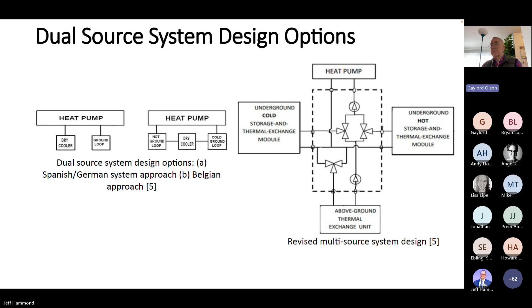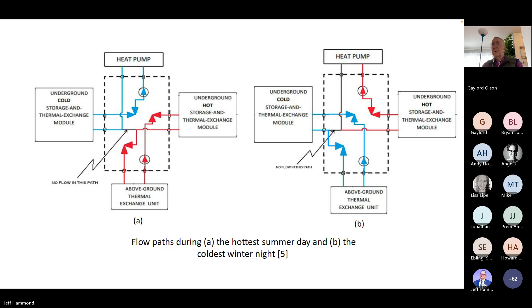Okay, so I think these are kind of repeats anyway, so I'm just going to zoom through these and you can look at them and think about them, but these are the 2 opposite seasons, hottest summer day and the coldest winter night. So you're getting warm water for the heat pump from the hot loop when you need it, and you're getting cold water from the colder ground loop when you need that. Hopefully you can have the water cold enough to have a very long duration of free cooling, so-called, or bypassing the compressor in the heat pump. So moving along to the next one.